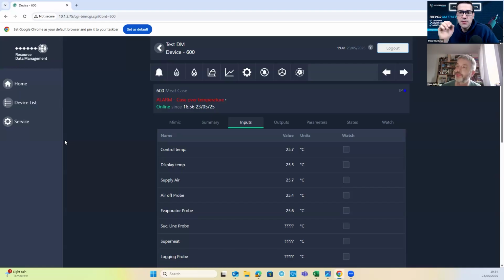So I'm going to watch what the superheat's doing. I'm going to want it to be stable. It's like we talked about in the last video. If I see the superheat's hunting up and down, I'm going to look. What's causing that? Is it the suction temperature bouncing up and down? Is it the evaporator temperature bouncing up and down?